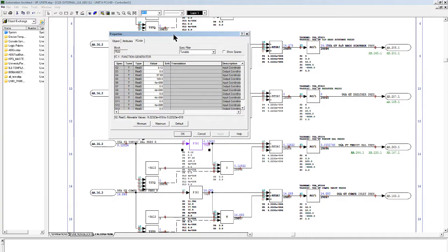So then, for example, say we had someone out there, transmitter locally, and they pumped it up to 100 PSI, and it was off, you would adjust this S4 value, your input coordinate. It honestly doesn't matter, from what I've heard when talking with ABB, if you adjust either the input or output coordinates, but you want to be uniform. You don't want to adjust your input here and your output here.